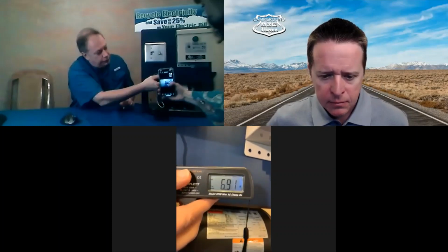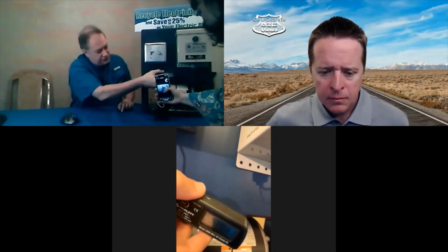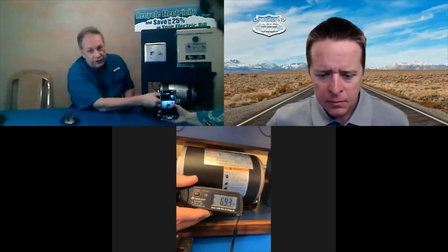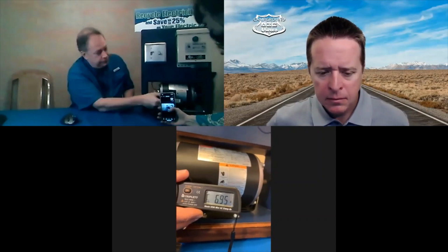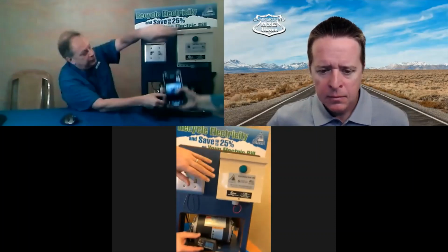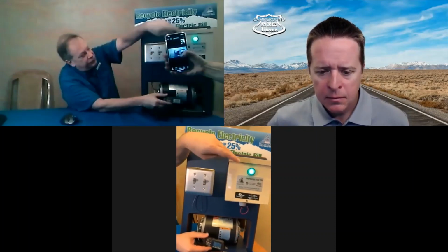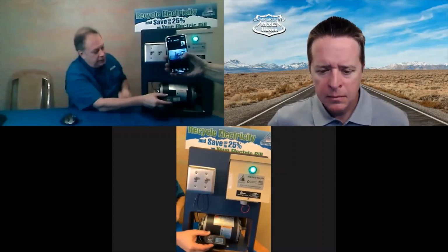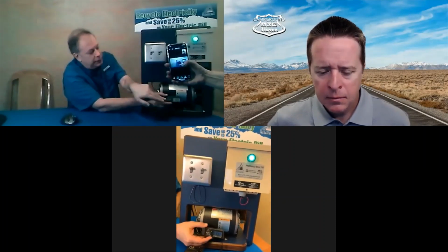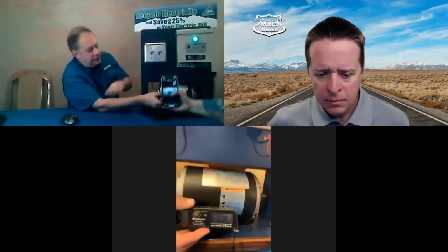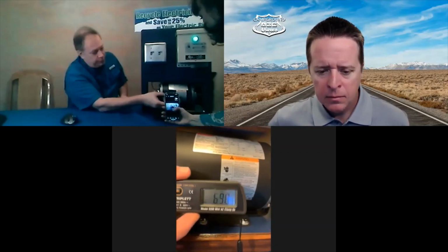All right, so you can see here that from the power company, we're buying about 7 amps, right? 6.9 something. And just to make sure everything's fair and square, we'll go down here to the motor, and you can see we're using the same current. Now, when we install the peak energy saver, we'll install it with the circuit breaker and turn it on, and you'll see the green light comes on, and the motor still gets the same current.